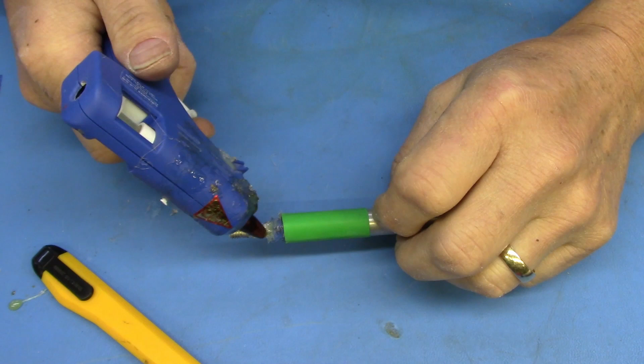The final assembly step is to put on the shrink tubing. Its purpose is to prevent a high voltage arc path from the end of the aluminum tubing to the aluminum rod. Position the shrink tubing just short of the 4 3/8 inch mark on the aluminum rod. Put a bead of hot glue around the end of the poly tubing in the 1/8 inch area. Quickly position the shrink tubing to the 4 3/8 inch mark and shrink it in place while maintaining its position. The heat gun should also warm the hot glue so the end completely seals.